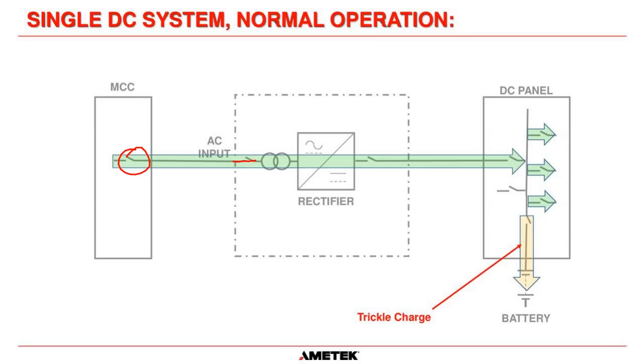Okay, so the power flows through AC to DC, and then it goes to the DC bus into the DC panel, and it's actually the charger that is feeding the load power to the circuits. The battery is just receiving a trickle charge. If you put an amp clamp around this point here, depending on your battery size, there's going to be a very, very small current. It's going to be between 0 to 1 amps DC going to your battery when it is in trickle charge mode, when it is fully charged. All of the current from the charger is basically going to be going through here to your load circuits. So that's how it would work in normal operation.